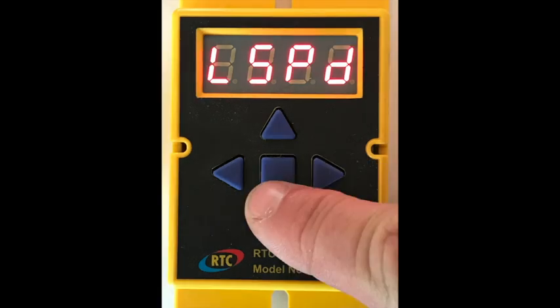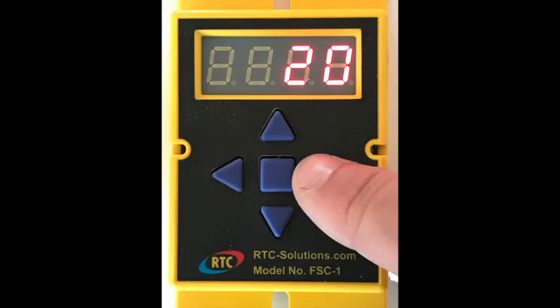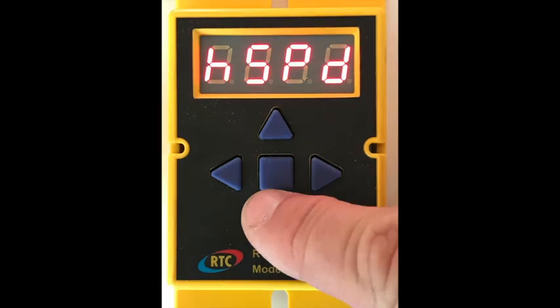The next menu is LSPD, or low speed limit. Setting this to 20, for example, will not let you run the motor slower than 20%. Just like low speed, the next menu HSPD is high speed and works the same way.